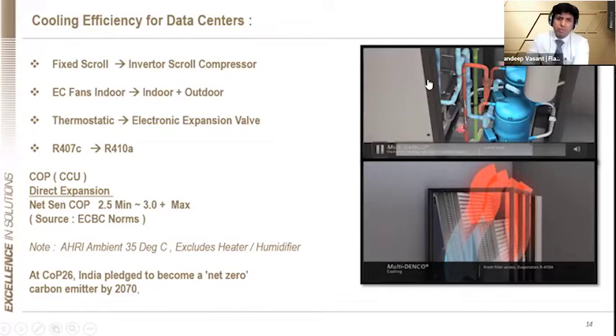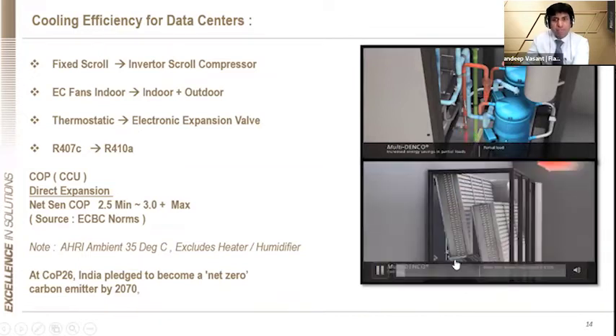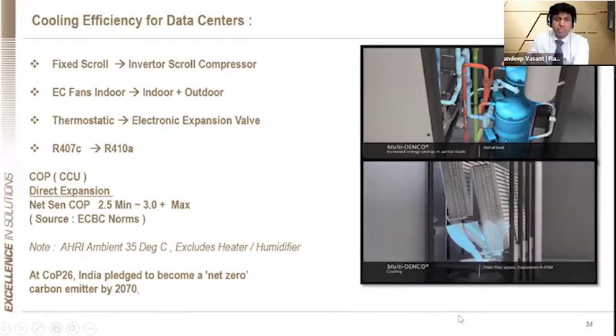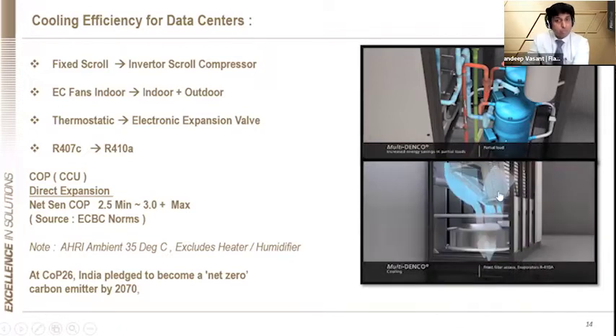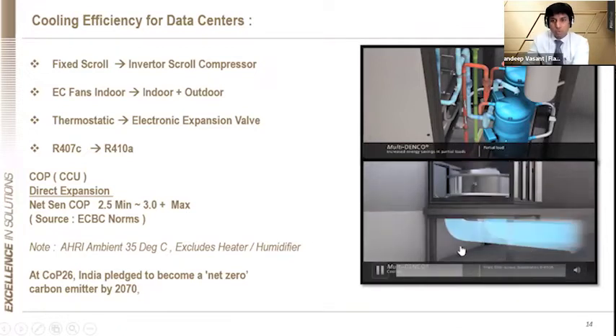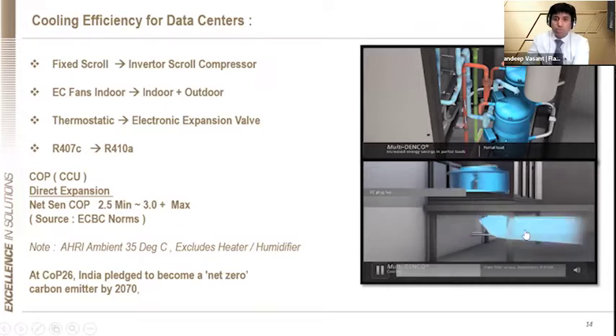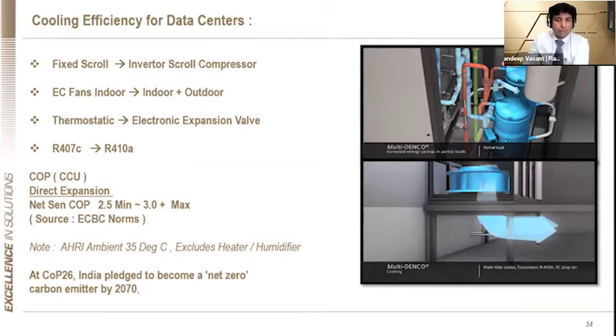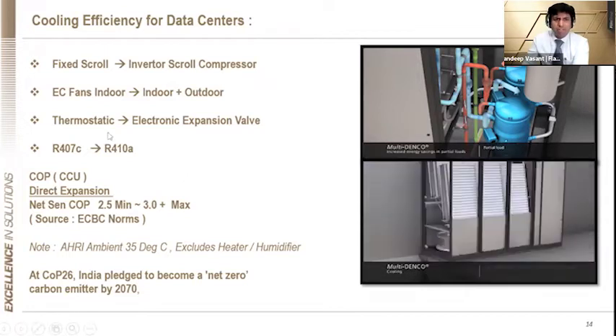What does an inverter compressor do? Lower power consumption at part load. Instead of an AC fan, today we are talking about the EC fan, an energy efficient, electronically commutated fan, both in the indoor and in the outdoor unit. Choosing the bottom throw in a data center would be better, because the cold air is high density and the hot air being low density would naturally go back to the top of the unit. Choosing a valve, either thermostatic or electronic expansion valve, and then we are also worried about the GWP and the ODP, so selecting a green gas as well.